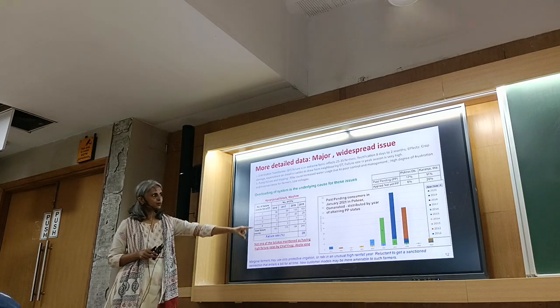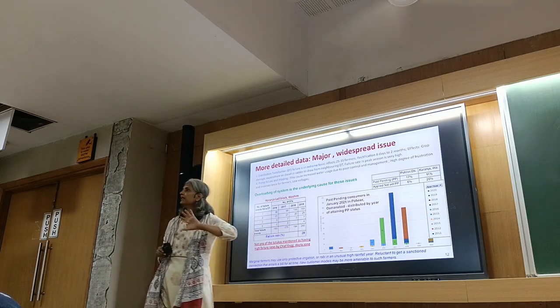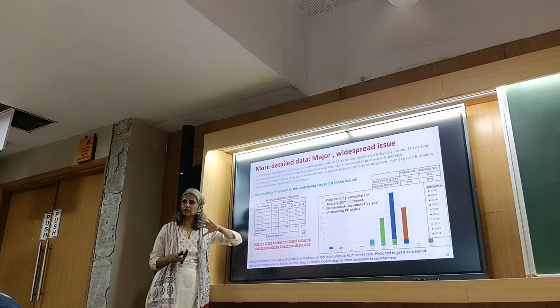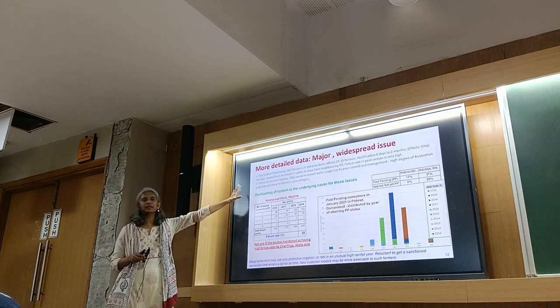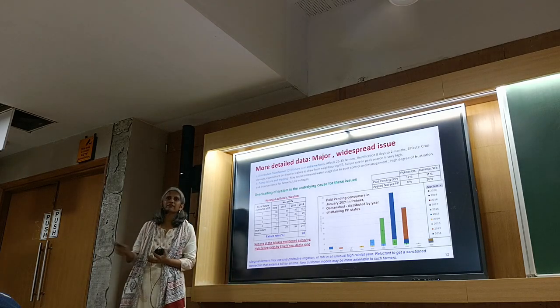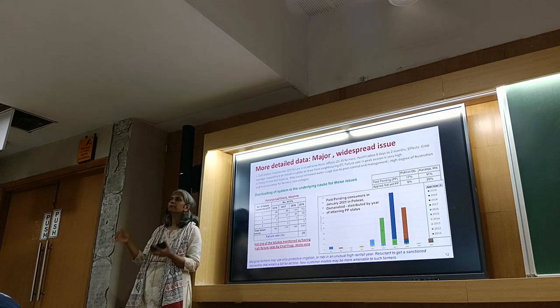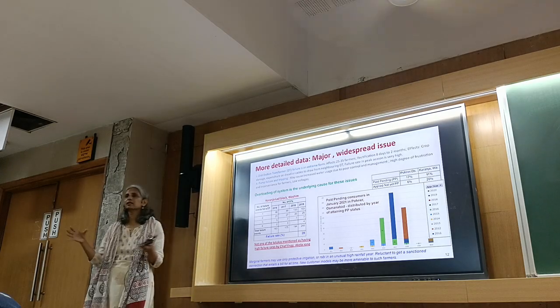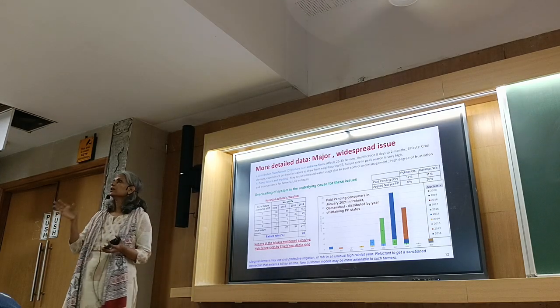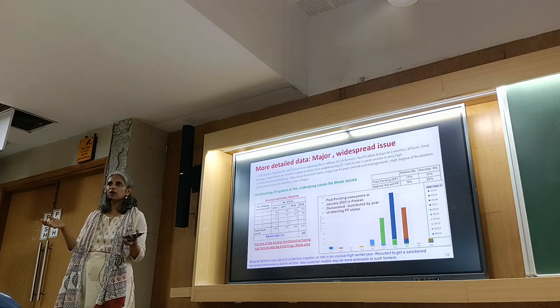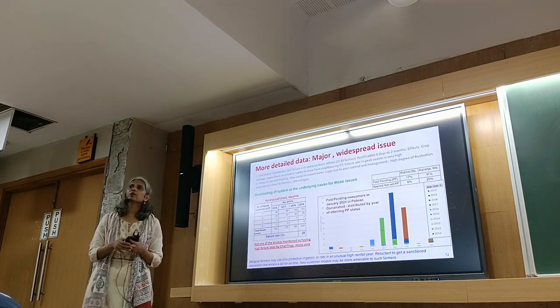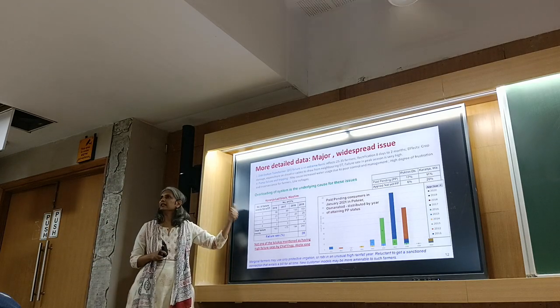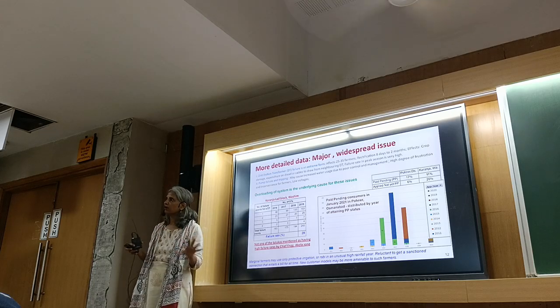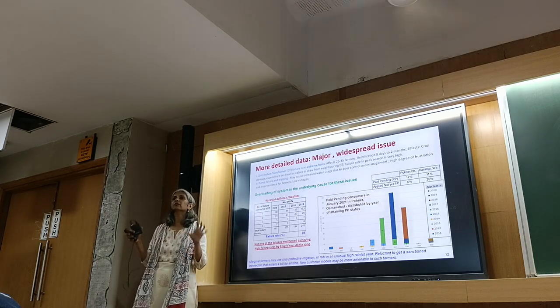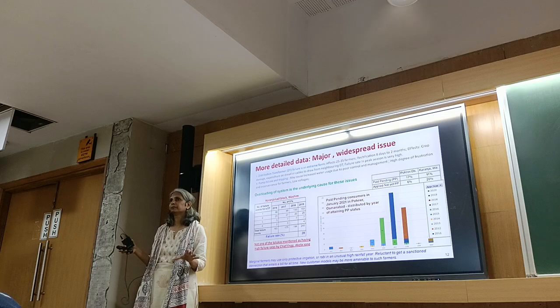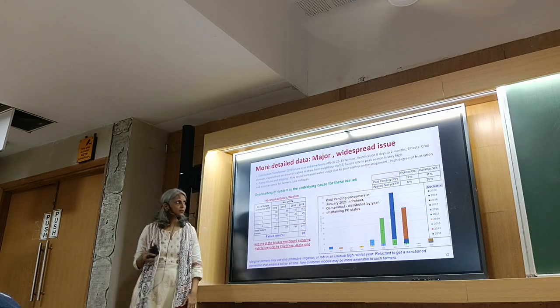The second issue is pump failure. So why do pumps fail? Because the voltage at the pump is low, and you get low voltage at the pump because the lines are too long for the particular load. So essentially, distribution transformer failure, pump failure and low voltages all happen because the system is loaded with more pumps than it is designed for. So the capacity is low.